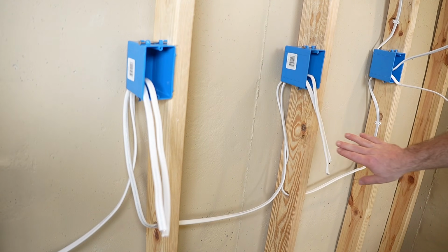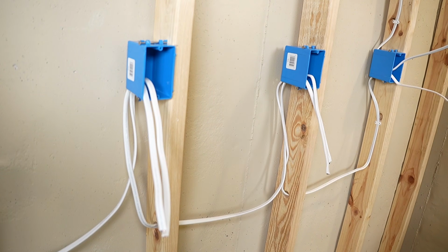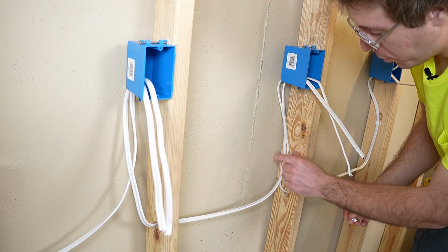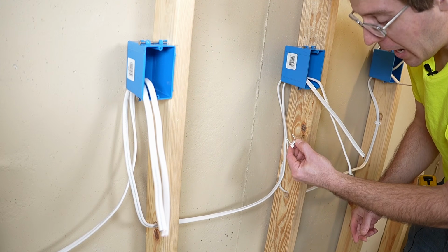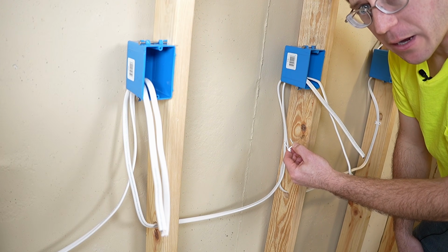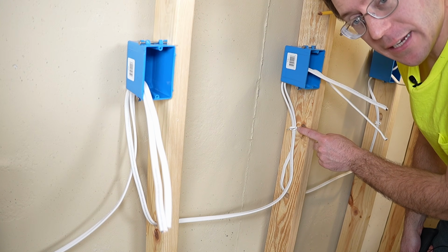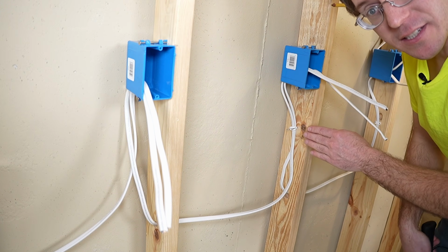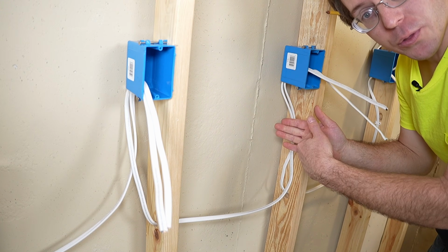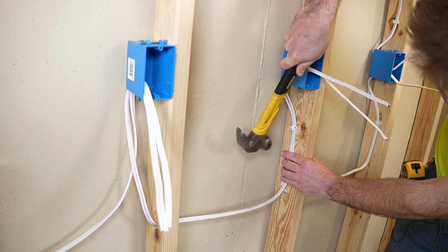And now with this one done, we need to go ahead and staple these two as well. This one right here, we can actually put both cables under one strap. It still has to be within 8 inches, however. Also, when you're strapping 2 cables at a time, make sure one of the cables doesn't slip and you drive a nail through the cable. That's always a bad day.